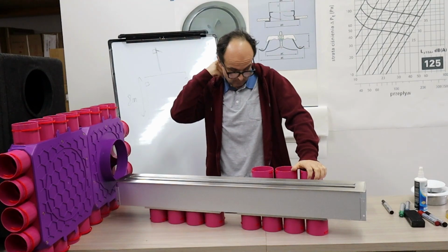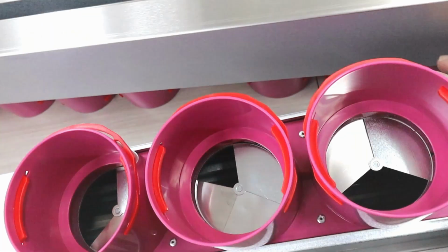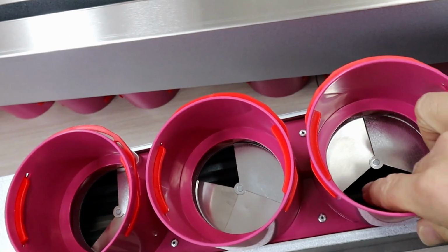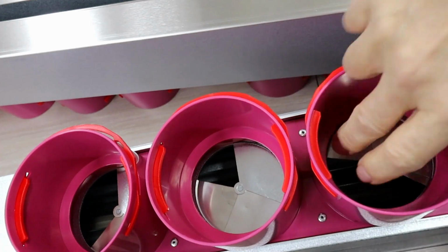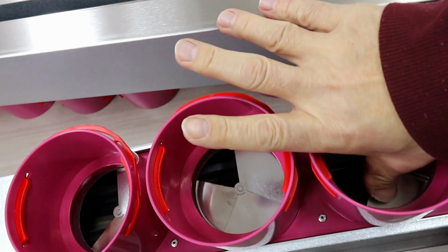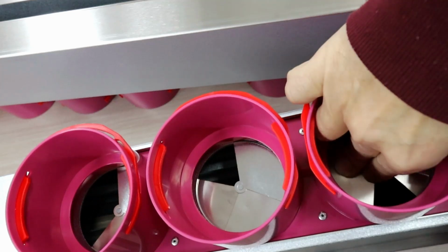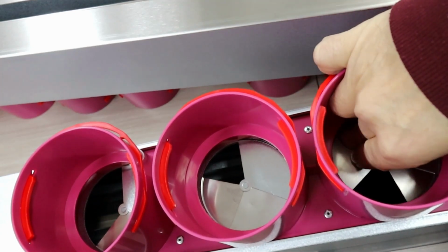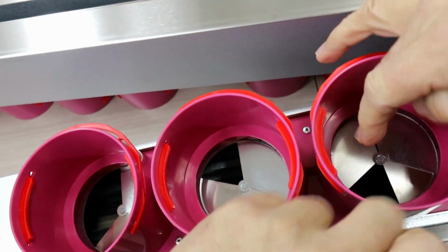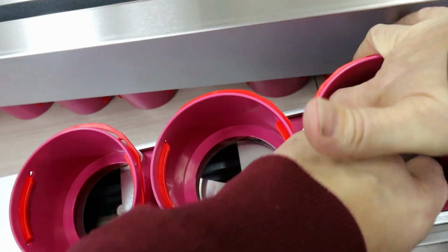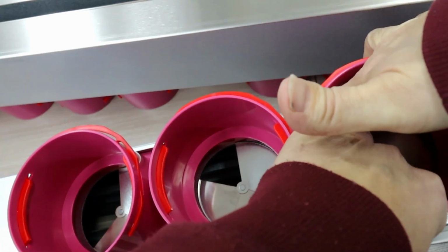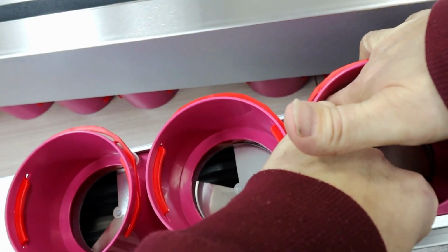to make them work. But I need to change the camera for that. Each linear diffuser here has something for flow adjustment. We can set the flow. It's a sort of damper. Of course, from this side it's more difficult to adjust because normally you adjust it from the front. Look, I can adjust the flow. I can completely close it or open it to say 30%.